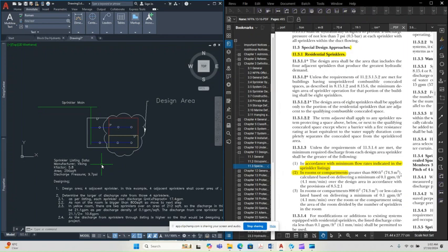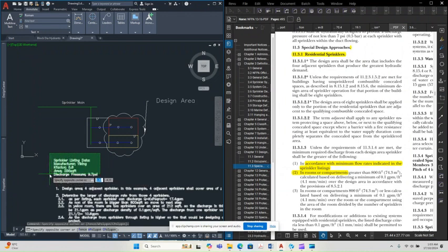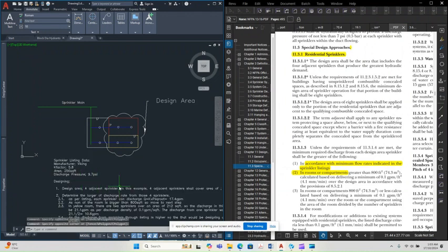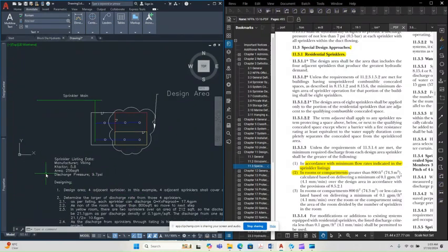One, you can propose listed sprinklers, or another option is that you can request information from the building owner to let you know who the vendor of the sprinklers is, and you can request at least four or five things: who the manufacturer is, and what the K factor, area of coverage and discharge pressure of the sprinklers will be.